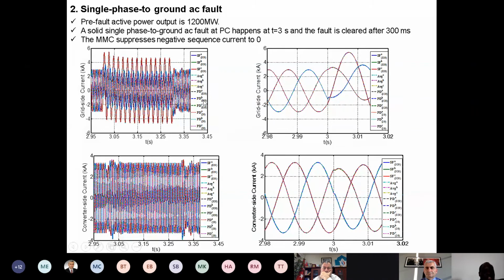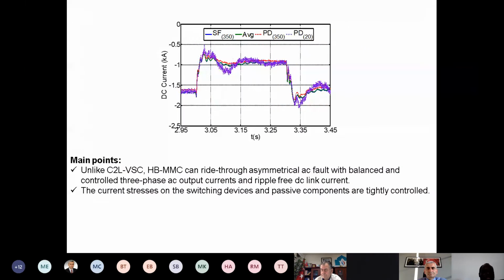In single phase fault, typically, if you have a two-level converter, you have 1 degree of freedom. You have options. If you maintain the output current balanced like that, you will see second order harmonic current in your arm and also in the DC voltage. But in the MMC, because we have two loops, we have a common mode loop and we have a differential mode loop. These two loops allow us to do two objectives. So we can maintain the current balance here, and also you can see here the DC current is clean from second order harmonics. All right.